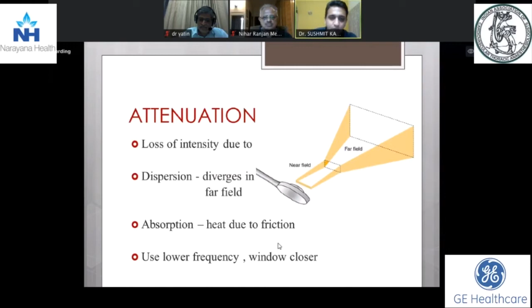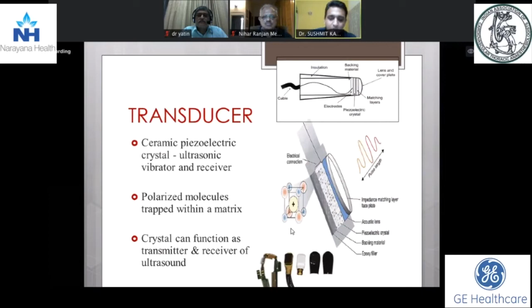An ultrasound transducer is nothing but a ceramic piezoelectric crystal which is used as an ultrasonic vibrator and a receiver. The entire echocardiography is based on the principle of piezoelectricity. That is, when alternating current is applied to the piezoelectric crystal, which is a polarized molecule trapped in a matrix, they start vibrating, converting electric energy into mechanical energy and producing an ultrasound wave. Similarly, this can happen in reverse, and the same transmitter can act as a receiver of ultrasound and convert it back into electronic signals.